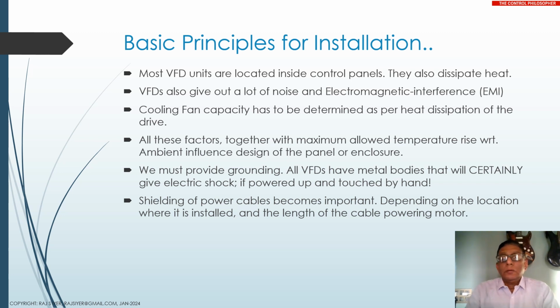installing a VFD. See, most VFDs are within electrical control panels, typically MCCs. Sometimes they can also be part of a PLC panel. Although VFDs are quite efficient, they are about 97% energy efficient, they still give out a large amount of heat. They dissipate quite a lot of heat. Means, let us say that if you have got a 10 kilowatt motor, it will easily dissipate in hundreds of watts. Okay, so we must take care of this by providing cooling inside the cabinet. Okay, then you must bear in mind that VFDs also give a high degree of noise and also electromagnetic interference.